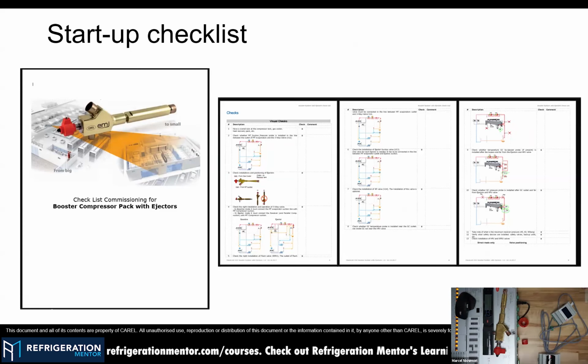Yes. Perfect. And one last thing that I want to share, I will share this document with you, Trevor. It is a checklist for the ejector installation. Normally, we have done this for the transcritical rack, but we have one dedicated just for the ejector. So a couple of basic things like what we were saying: the position of the ejector, the wires, how it's installed, the position of the probes, and so on. You just make sure that you have checked everything before turning on the system. And I'm pretty sure that if you check all the boxes, when you turn on the system, it will be really plug and play and you will just see the system running.